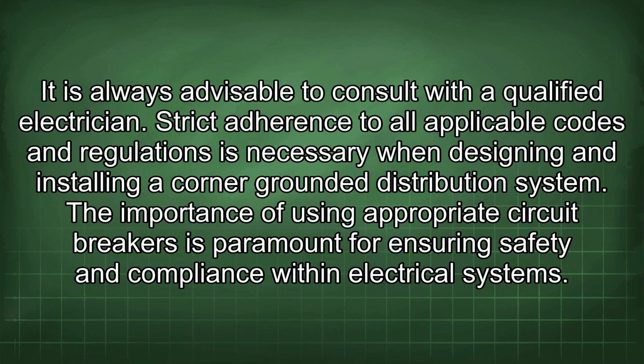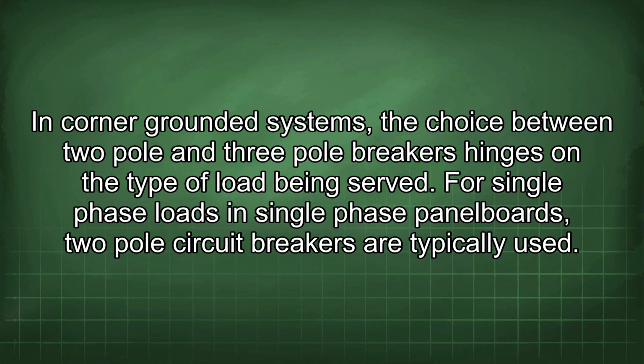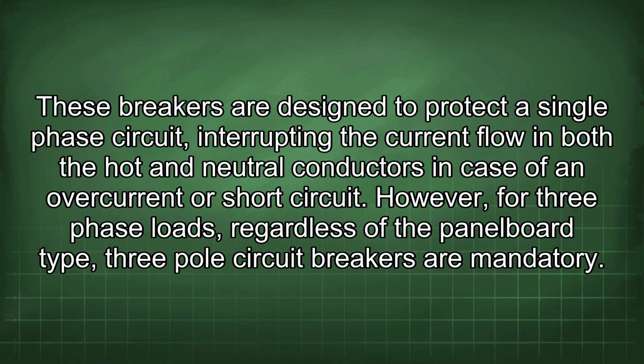The importance of using appropriate circuit breakers is paramount for ensuring safety and compliance within electrical systems. In corner-grounded systems, the choice between 2-pole and 3-pole breakers hinges on the type of load being served. For single-phase loads in single-phase panel boards, 2-pole circuit breakers are typically used. These breakers are designed to protect a single-phase circuit, interrupting the current flow in both the hot and neutral conductors in case of an overcurrent or short circuit.